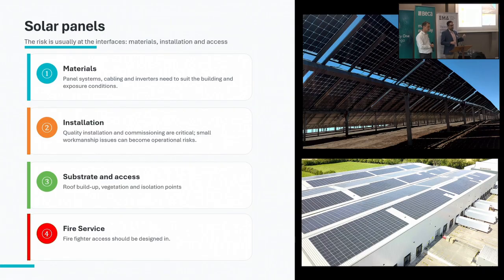If you put them on a field, how much combustible material is below it? In Australia, they're out in the desert often or dry spaces, so they tend to keep it very clean. Here, we'd keep grass to about 15 centimetres. Once you go above that, the height of the flames, if it does occur, becomes harder to control. So it's about controlling those levels.